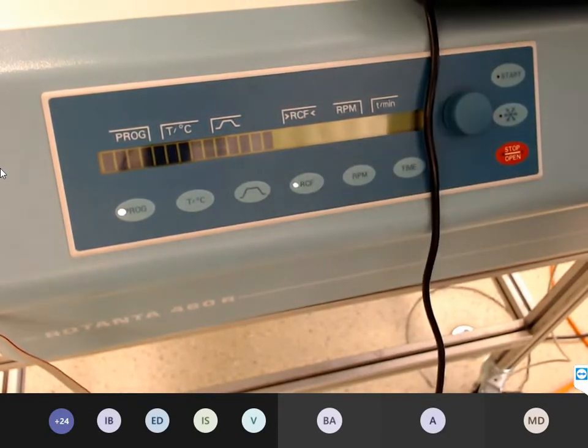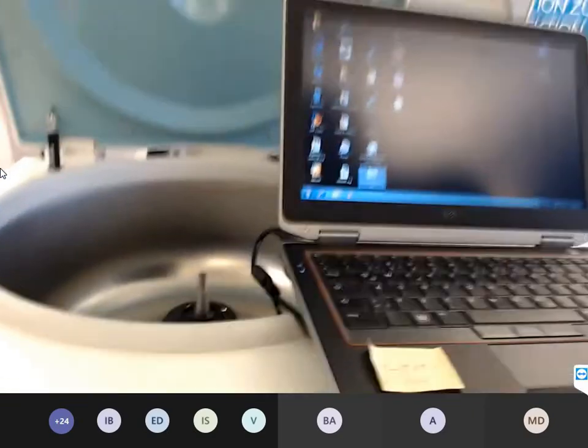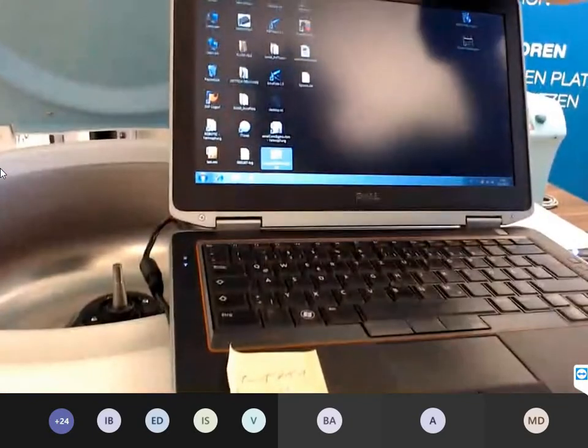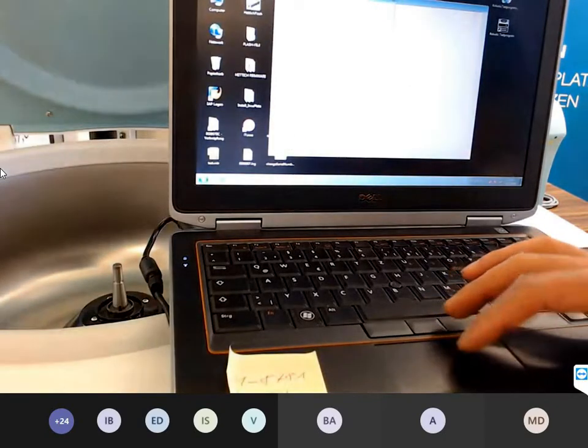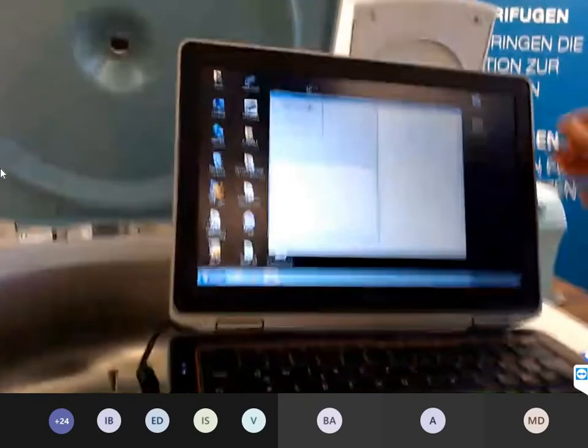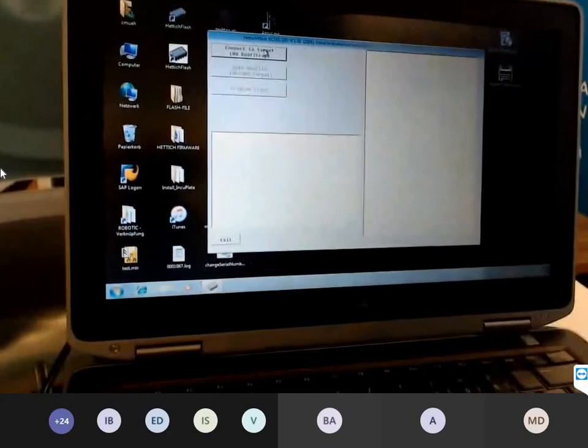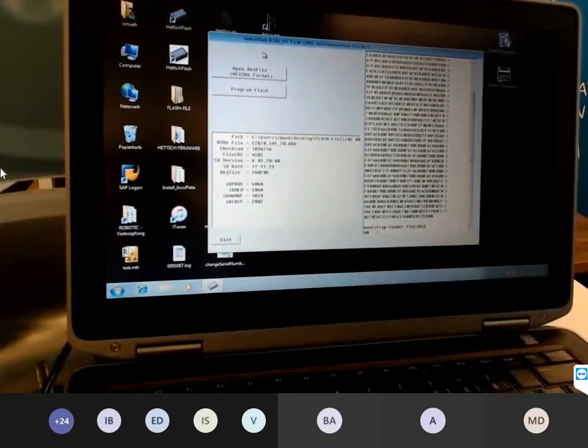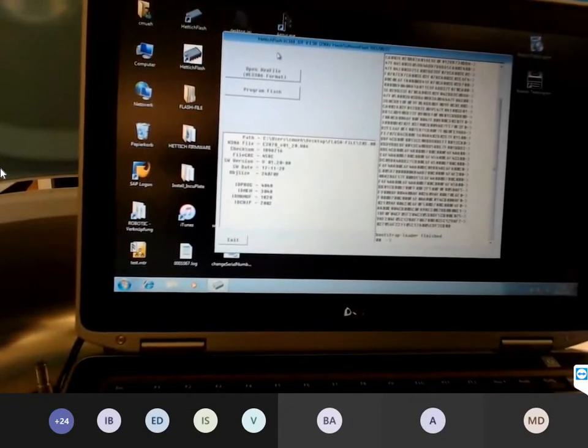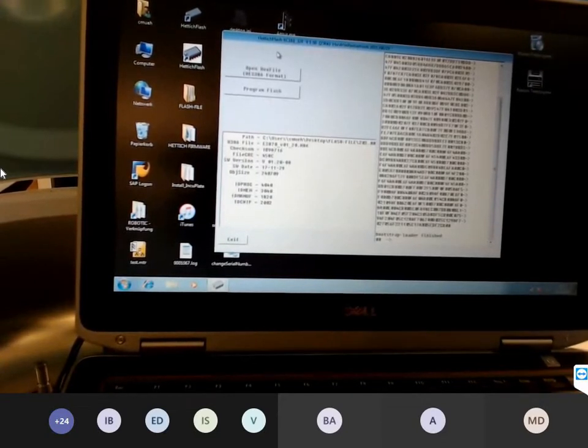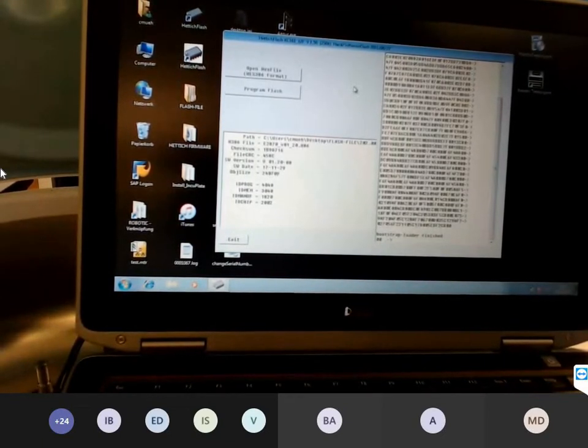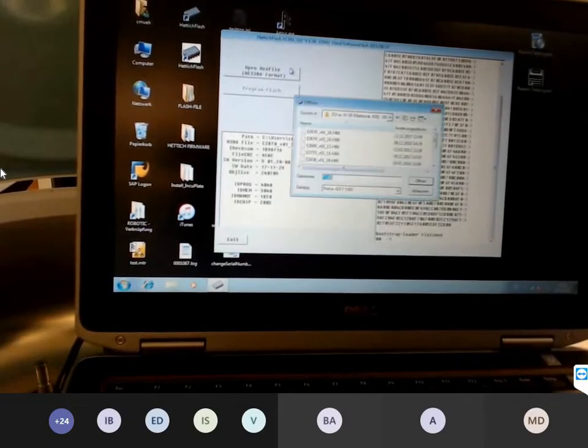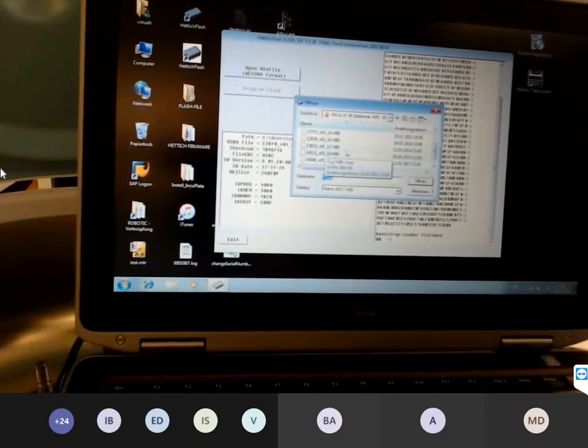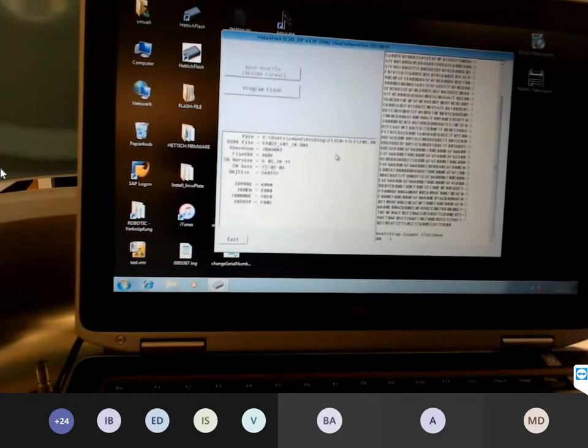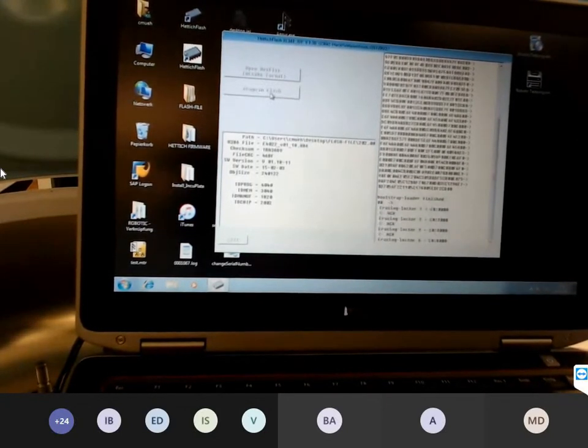So open the Hettich Flash 2 software. It's also included in this kit. Open the Hettich Flash. Connect to target. And now we have a communication. You also find this procedure in the service manual. So, for example, we have here the software version 1.20. We make a downgrade, and now we can flash the old one, for example 1.18. Choose 1.18 and start the flash.